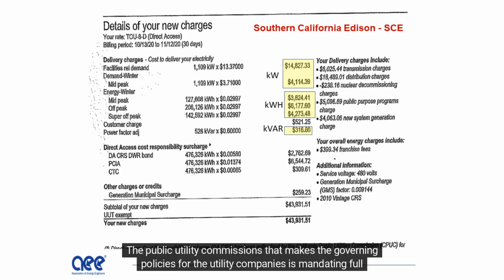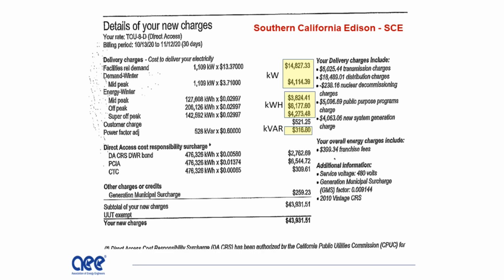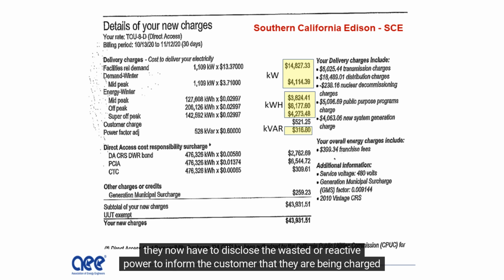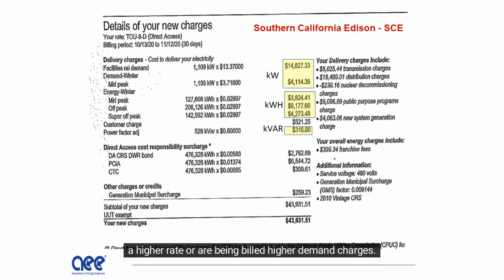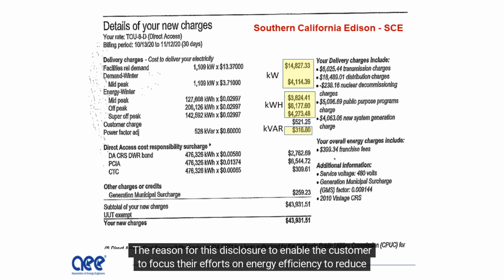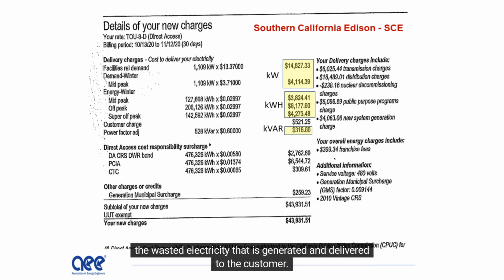The Public Utility Commissions, which make the governing policies for the utility companies, are mandating full disclosure on the utility bills. They now have to disclose the wasted or reactive power to inform the customer that they are being charged a higher rate or are being billed higher demand charges. The reason for this disclosure is to enable the customer to focus their efforts on energy efficiency to reduce the wasted electricity that is generated and delivered to the customer.